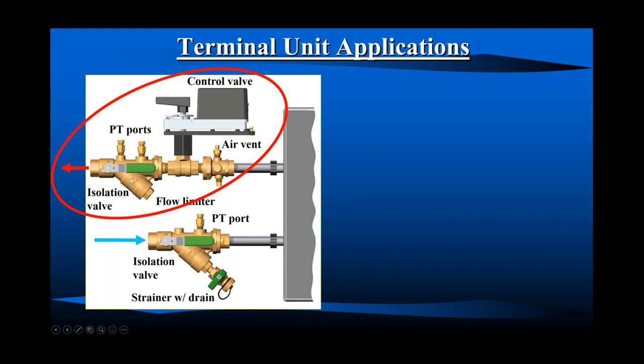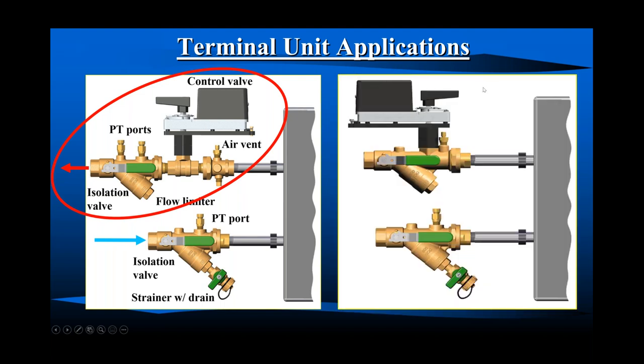Well, there's a moving part there, right? It's got a spring, it's a piston, if you will. And of course, our control valve is a moving part. So some folks put them in one valve body. There's the same as before, except the union, there's our control valve, and it's the same valve body as the flow limiter. So two moving parts in one valve body. So yes, they do work in harmony. They do not fight each other. These two moving parts are advantageous to the performance of this terminal unit.